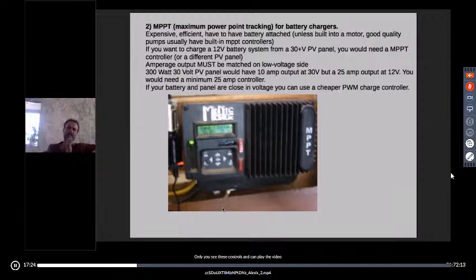You need to, with any of these charge controllers or voltage regulators, pay attention to the amperage on the output side. For instance, if we had a 300 watt, 30 volt PV panel, that would have about a 10 amp output at 30 volts. But if you're going to drop that down to 12 volts, let's say you've got a 12 volt battery set, you're going to be pushing 25 amps coming out the output side of that. So you need a charge controller rated to a minimum of 25 amps. This one you're looking at here is a 30 amp, forget what they call it, their smaller version of the Midnight Solar controller.